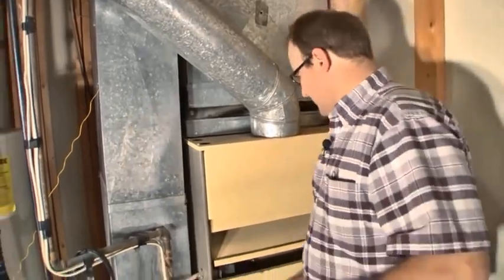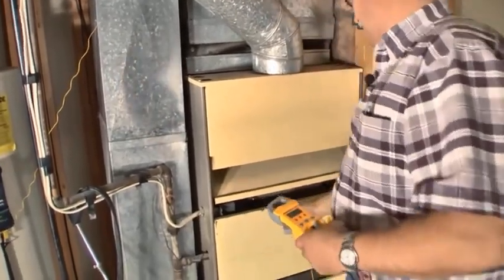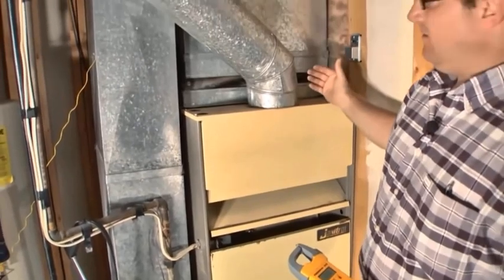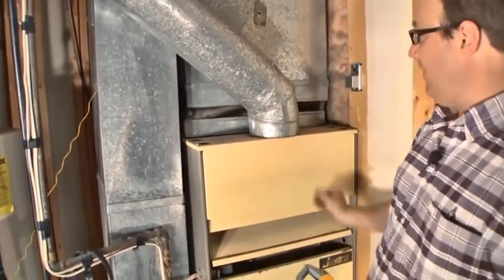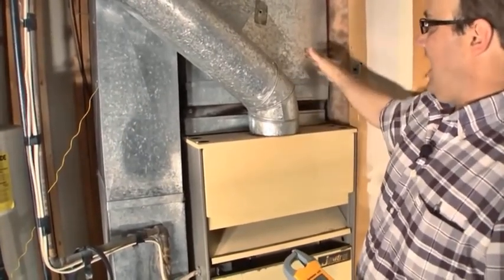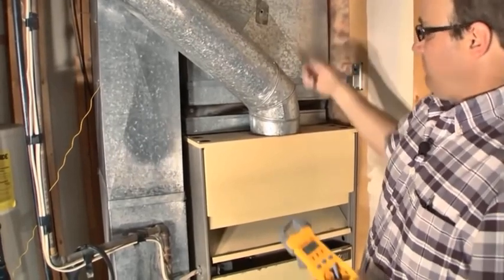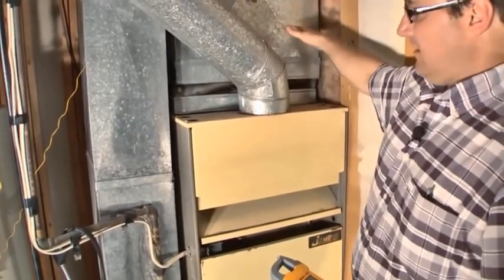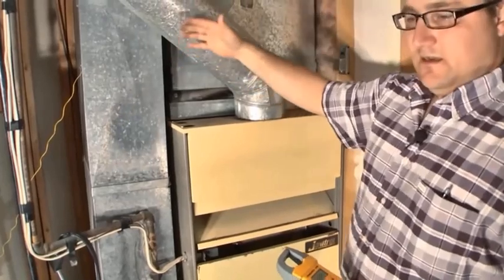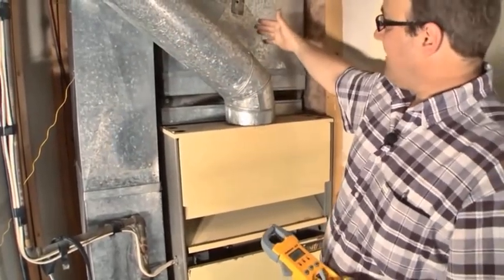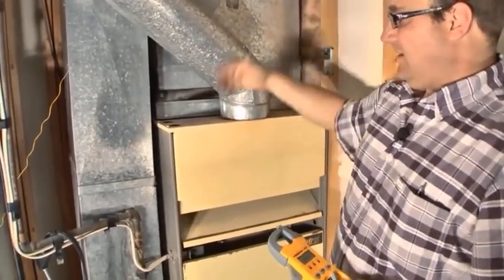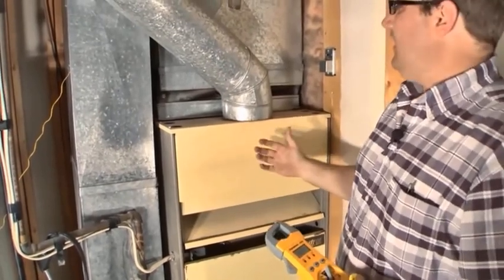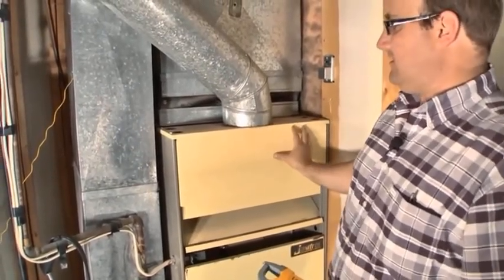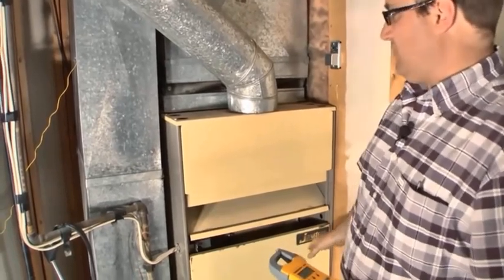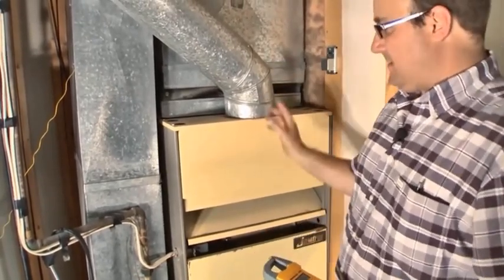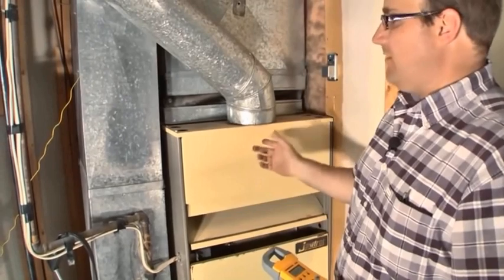And what this furnace will do, in fact it just did it, it cycles on high limit because we don't have enough airflow. It gets so hot that it turns the gas off, which is right about 230 degrees. The nice thing about that is when it cycled off at that, I know that the high limit on this works, and it's around 230 degrees that this thing shuts the gas off because it's getting too hot, and keeps the fan moving, the air moving with the fan.